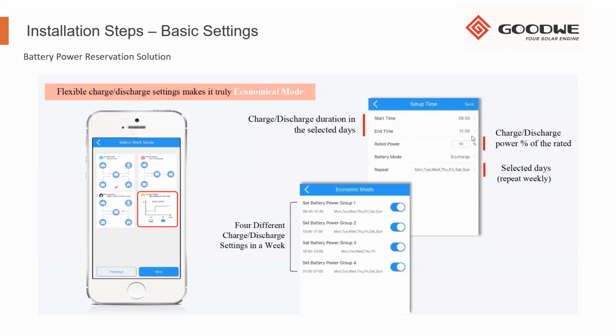So should you have a smaller battery pack that only gives you 50 amps, setting it at 10% will mean a maximum charge rate of 5 amps. For our backup only mode, this is the default setting, which is 10%. That's just a slow UPS charge.